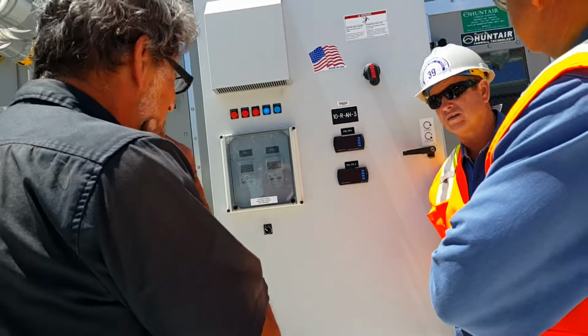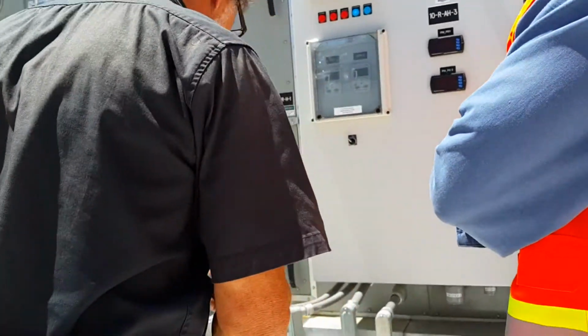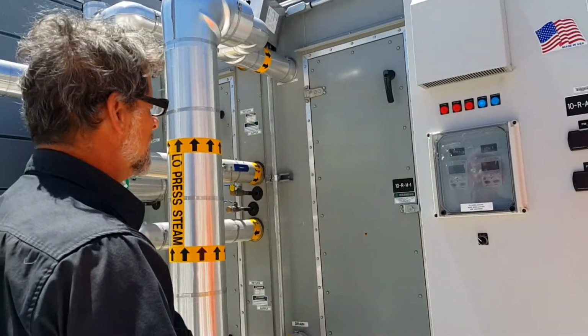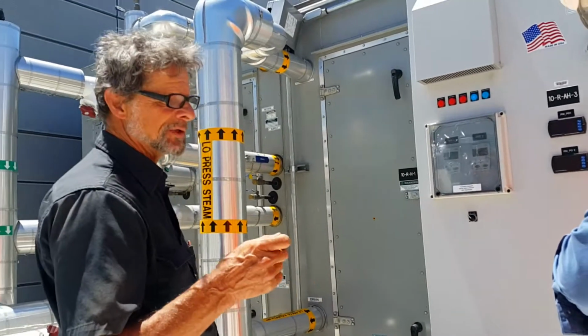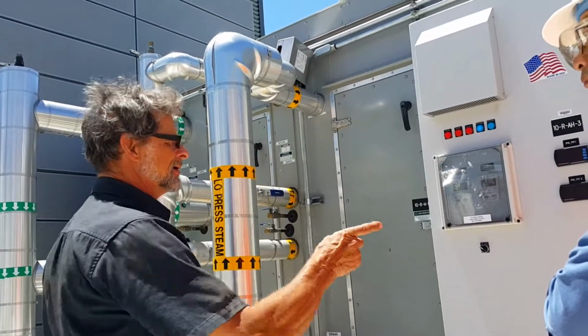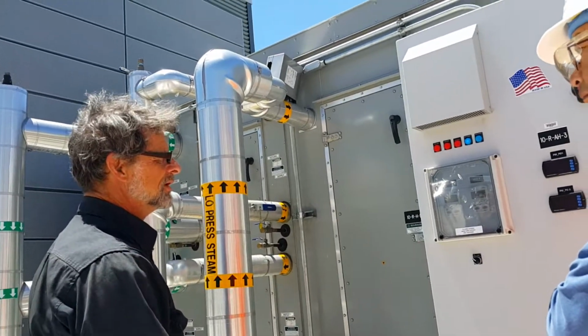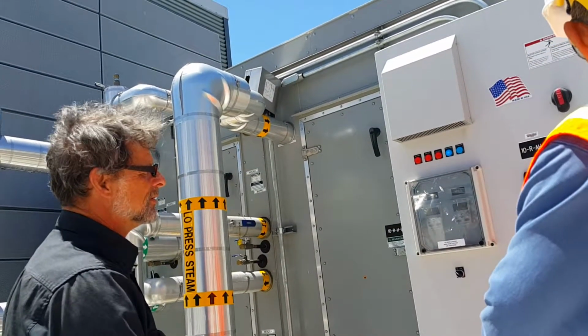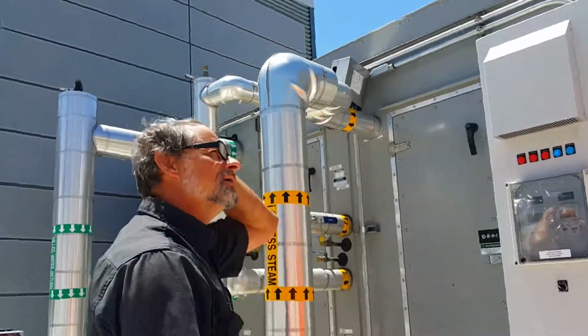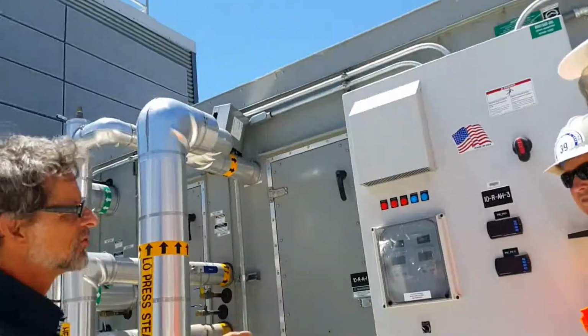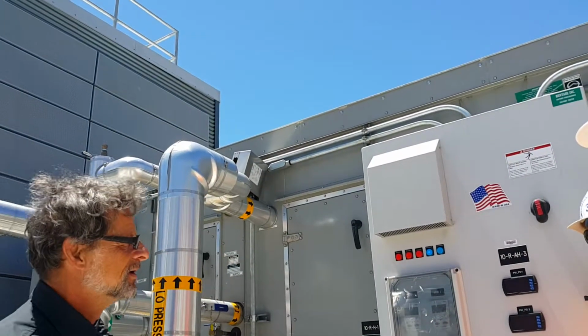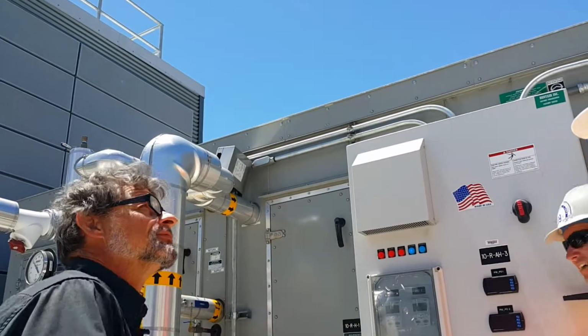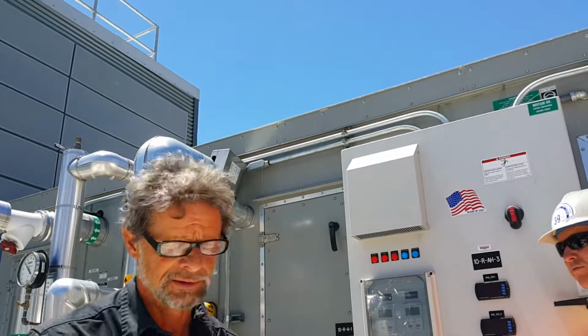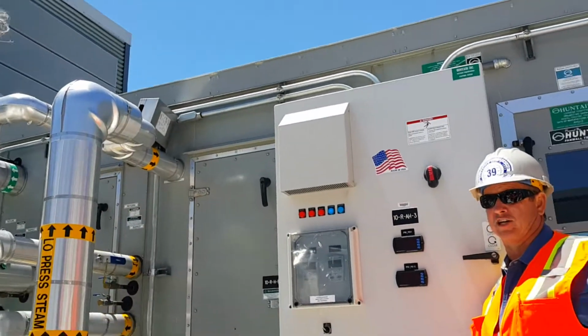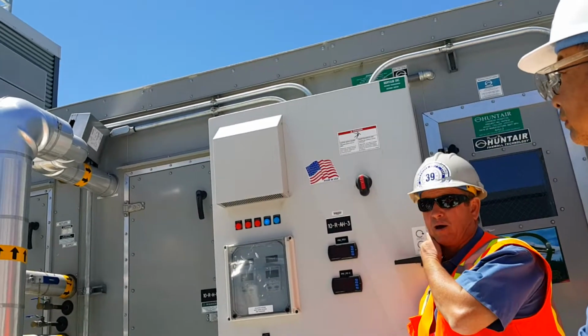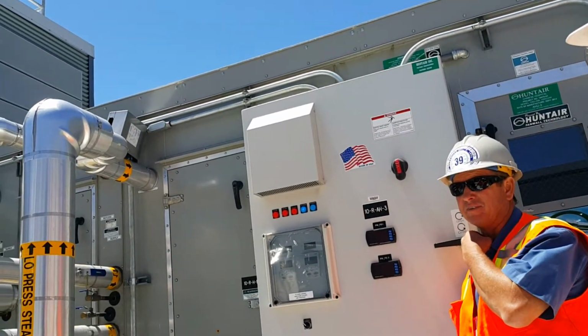This is the place to put it, because most of the hospitals I've started up the last few years all over the Bay Area, instead of doing this, they put the steam outlets right in the operating rooms, with their own individual controls. They send 55-degree air in there, and then they hit the steam, and it freaks the doctors out. It just looks like the place is on fire. We do have them in the building too, but not in the ORs. In the ICU ward, we have steam injectors on the sixth floor, but we're probably going to turn them off once it's all said and done. We don't need them.